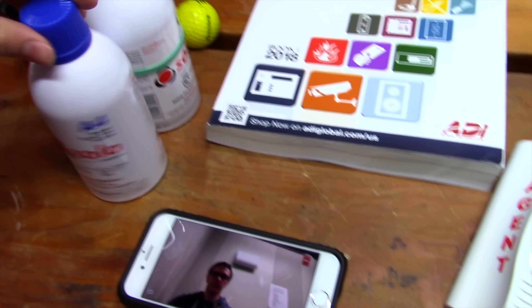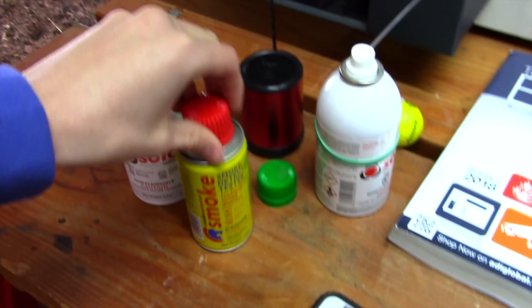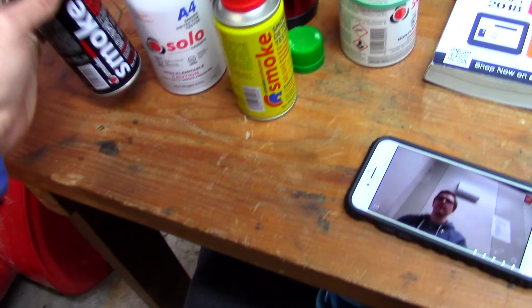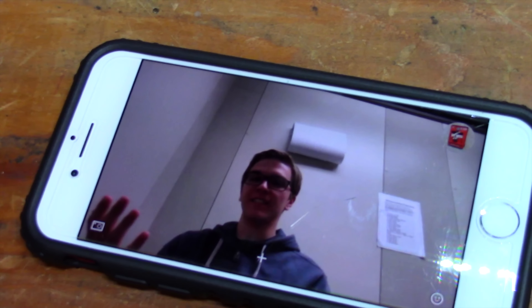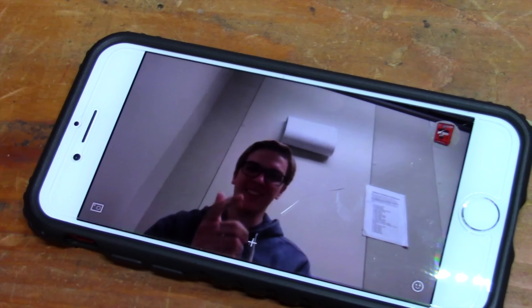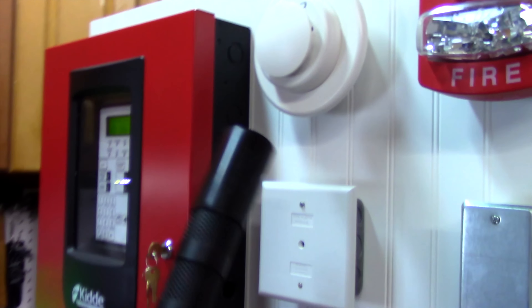I've got some options to test the smoke detector. I got the Solo A4, got the little yellow can of smoke, and then we've got the smoke saber. What do you think I should use? Based on your video going over all of those devices, I loved watching you fling out the saber. Yeah, everyone likes that. I think we need to see that one more time. Okay, you ready? Here we go. Alright, that's so cool. We'll go ahead and just kind of spray this at the smoke detector.